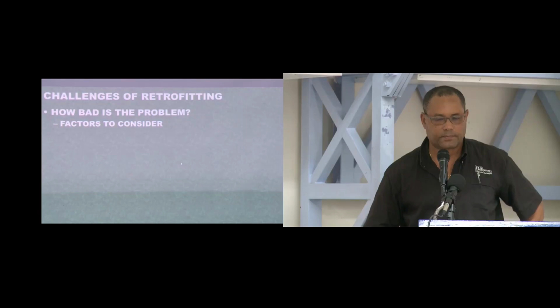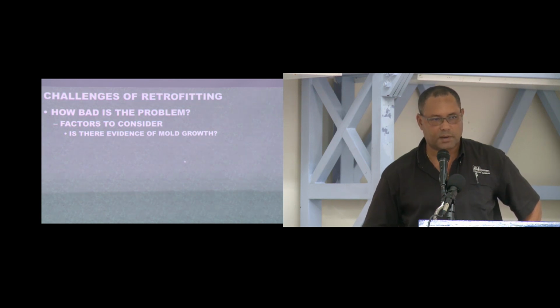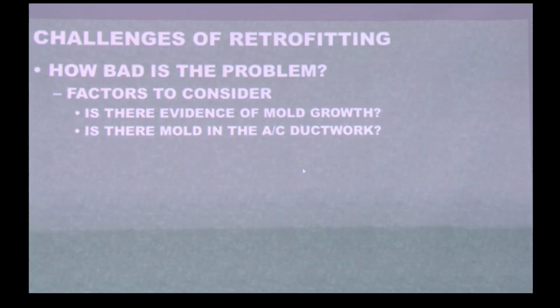And so, retrofitting challenges. I do have to wrap up shortly, so I'm not going to go too long on this. So how bad is your problem? If there's mold growth, well, you've got a problem, because chances are your employees have seen it already. If there's mold in the AC ductwork, then if it's fiberglass ductwork, you need to replace it. If it's galvanized, you can actually call in a cleaning service and deal with it.